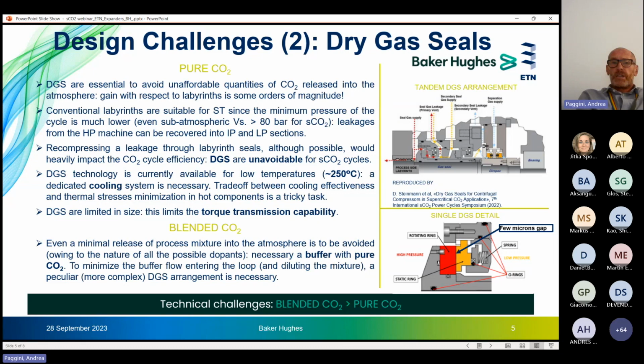Stefan also mentioned that dry gas seals are limited in size. So if you think to scale up a CO2 expander beyond certain limits, as a matter of fact, there is currently a torque transmission capability limit. So you cannot transmit the torques that typically you have in steam turbine trains. What I've just said applies to the case of pure CO2.